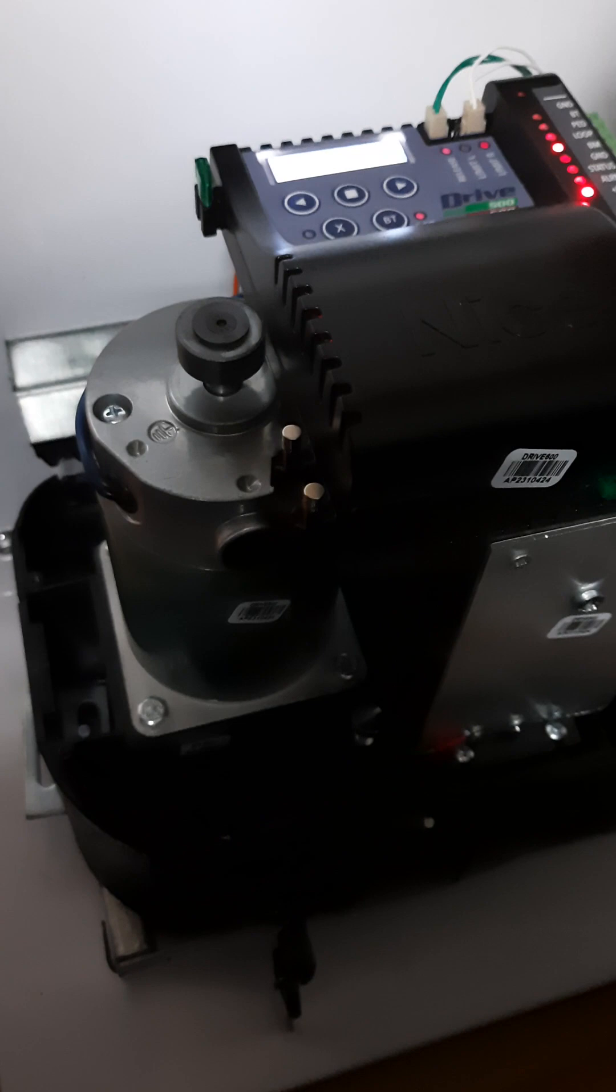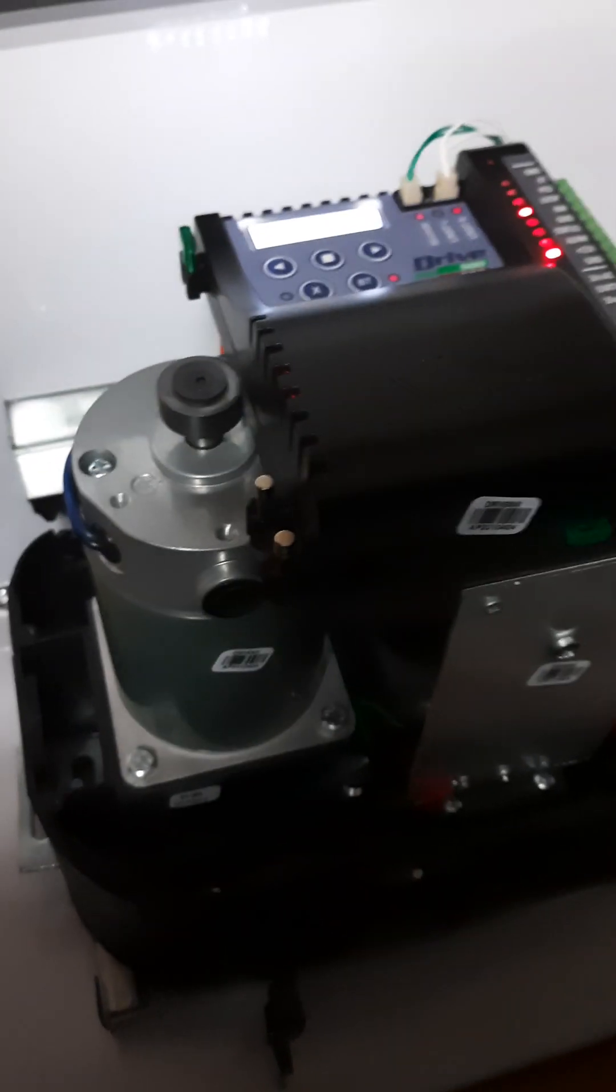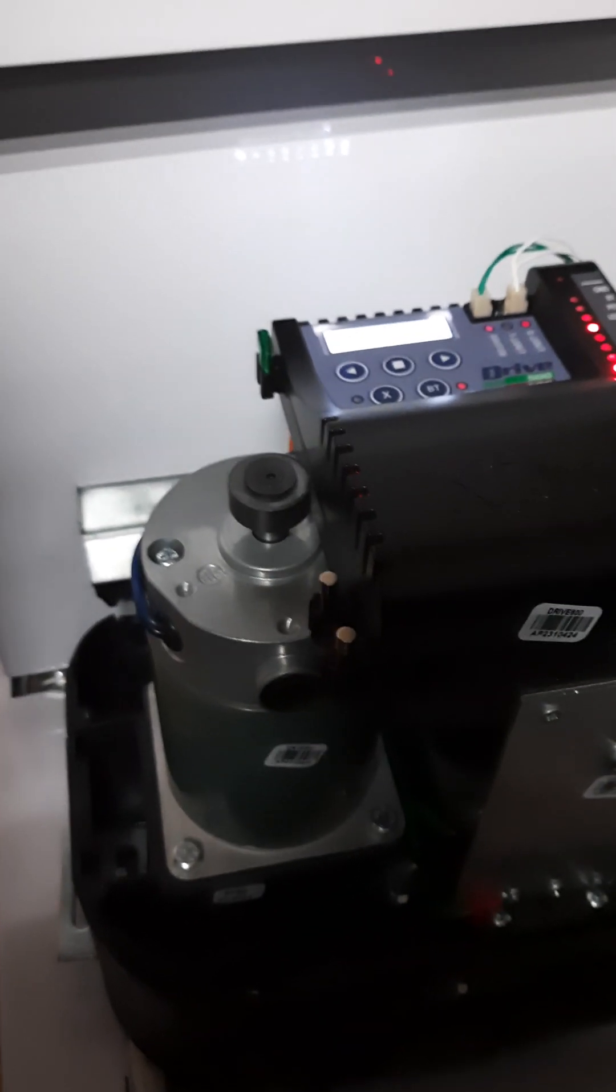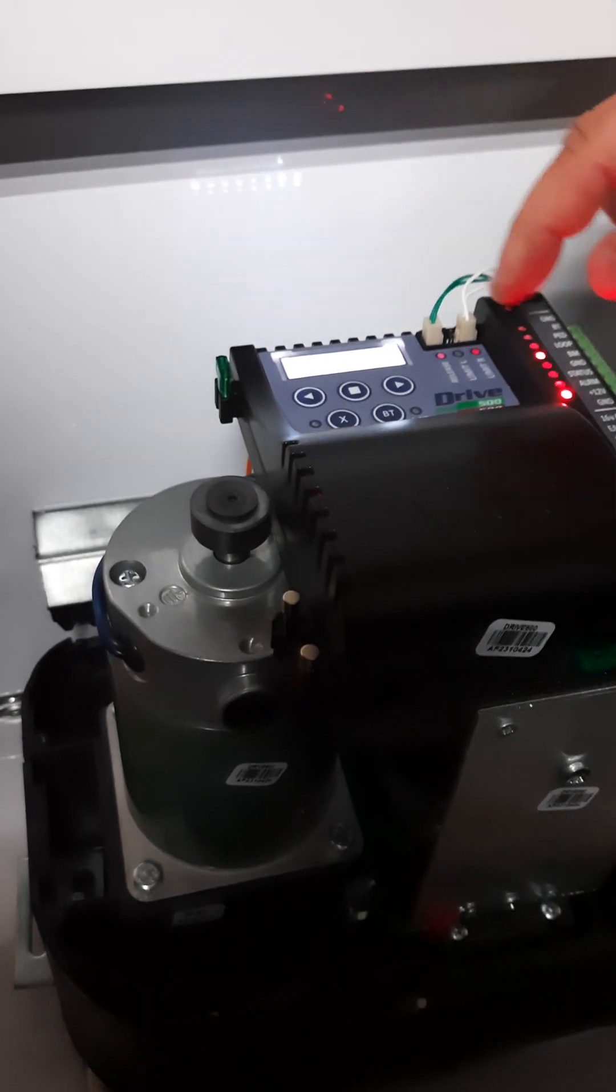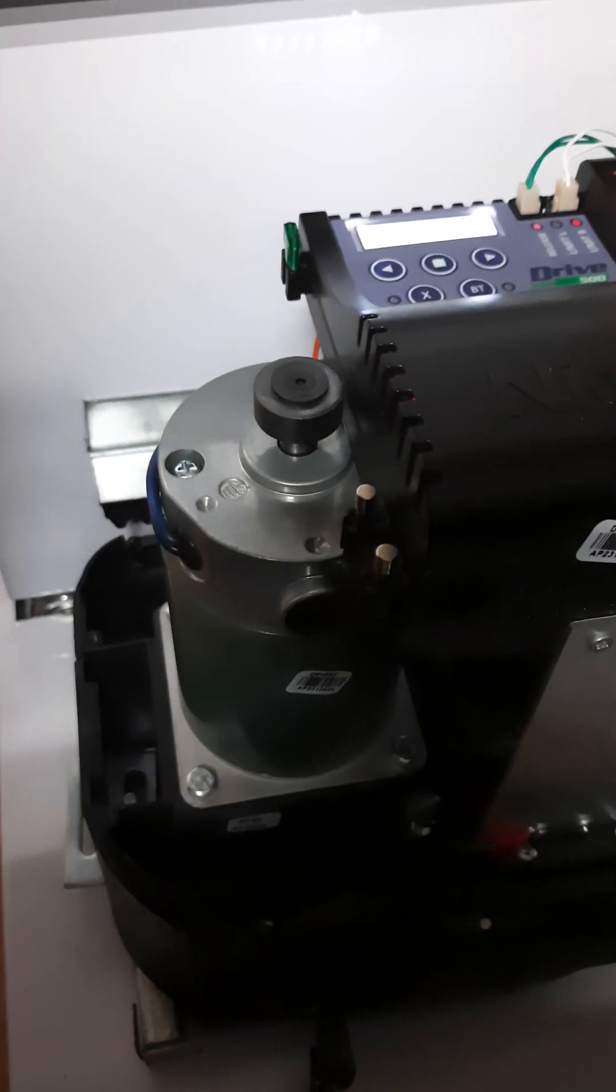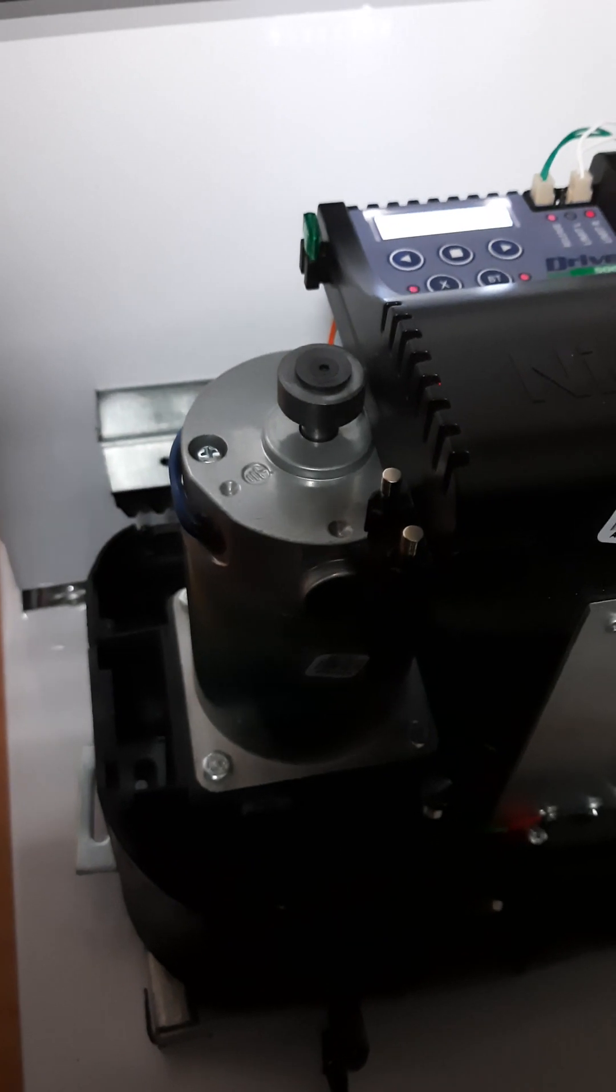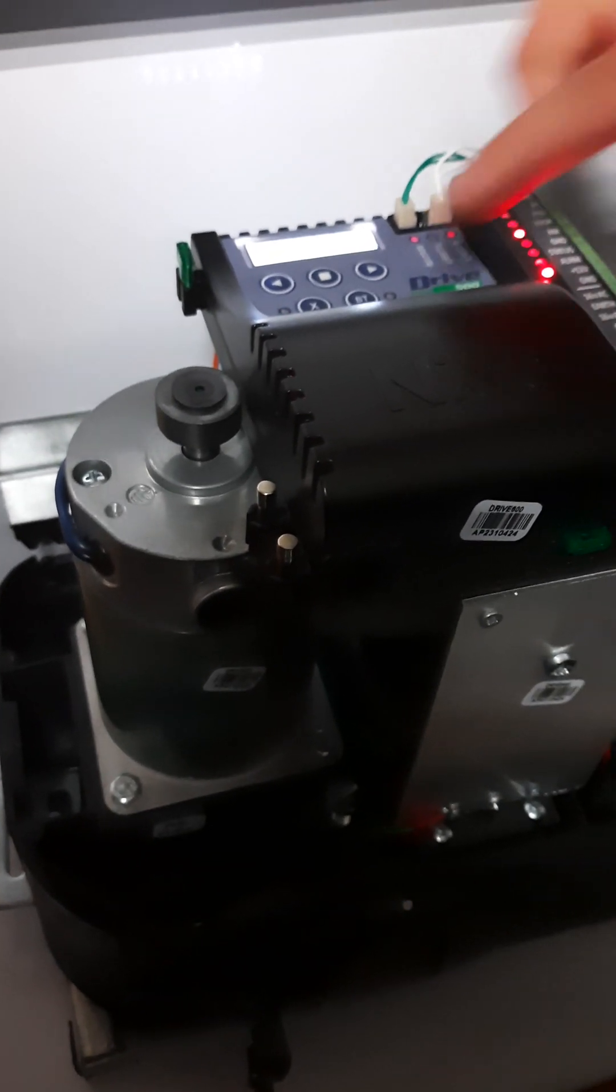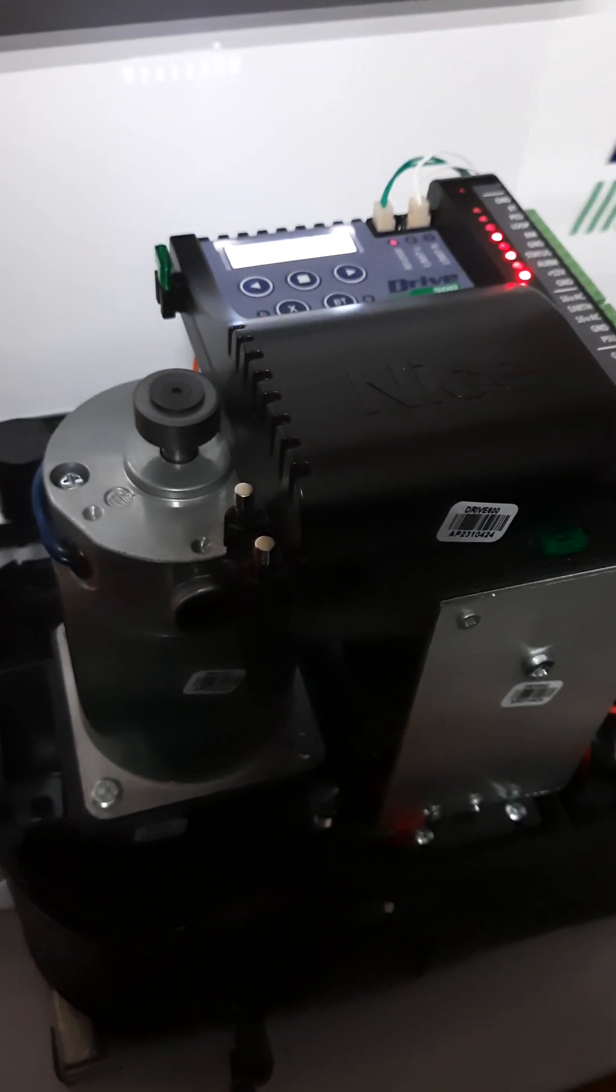Enter. Now it is asking me which channel do we want to use. So BT is the full channel, full open button trigger. Remember the way to program remotes is always press the remote button first. Because when you do that, it means that this receiver can't program in someone else's remote by accident. You press the remote button first. Then you go quick learn. Here we go. Then you press the switch. It says press the switch. It is complete. Now we can exit the programming menu. And you can just test if our remote is working.